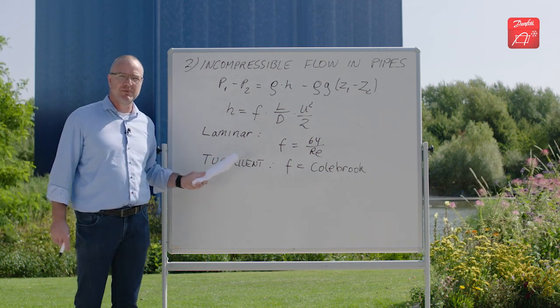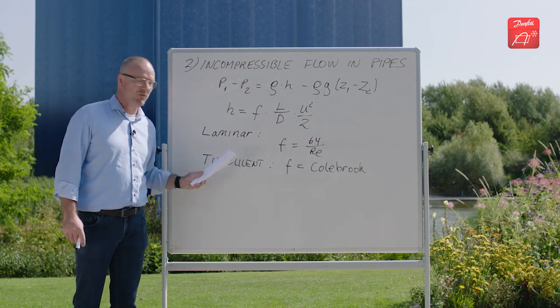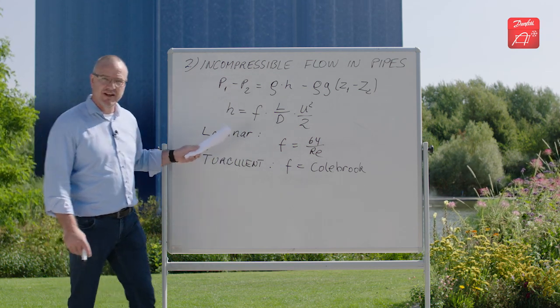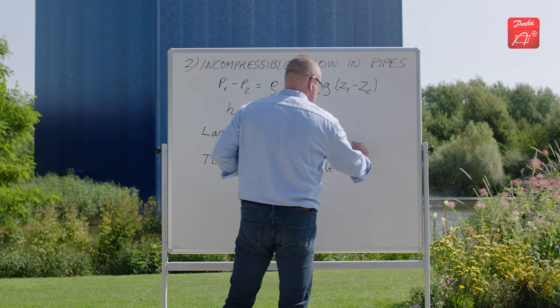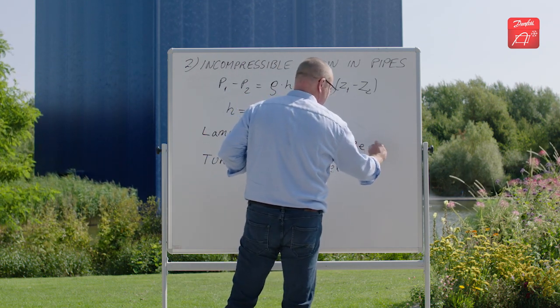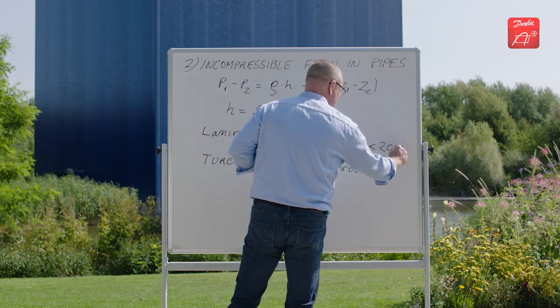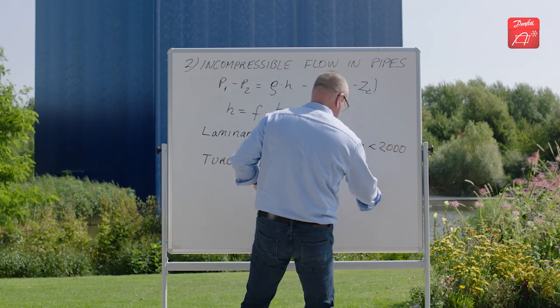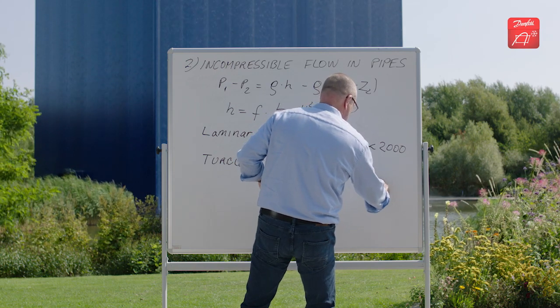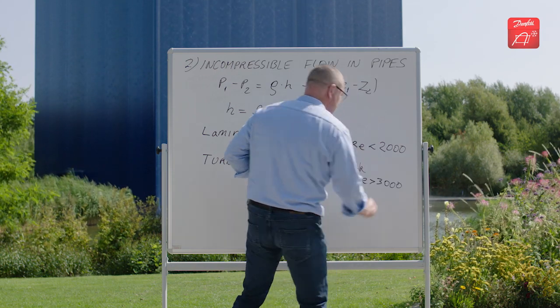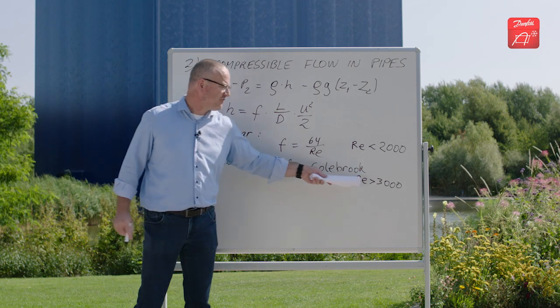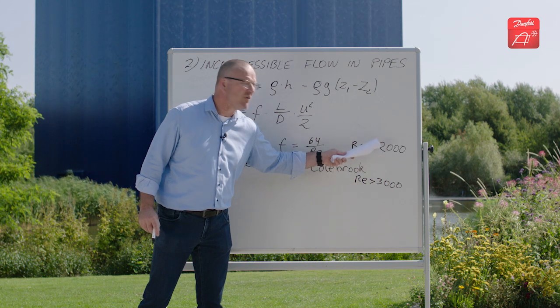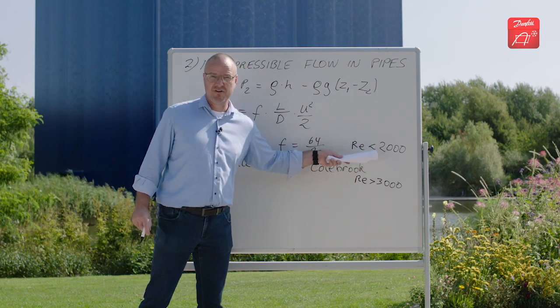In CoolSelector you actually have the possibility to decide yourself when it switches from laminar to turbulent. But the limits we have put in as default is that it is laminar when the Reynolds number is lower than 2,000. And it is turbulent if you have Reynolds number larger than 3,000. So, in between here you will actually have an unknown area.